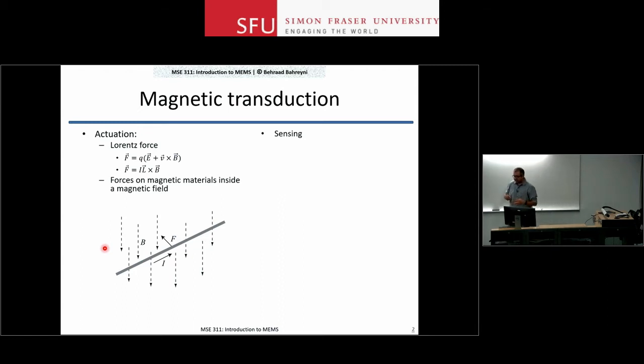So you can have proximity sensors that are not affected by humidity, dirt, grease, or any of the things that normally disturb an optical or acoustic proximity sensor. The magnetic one is not affected by that much, so industrially these are very robust sensors. Because of the demand, people have found many different ways of measuring them.